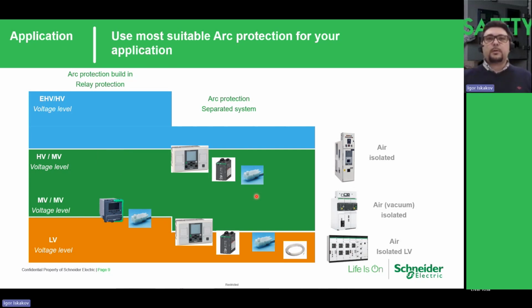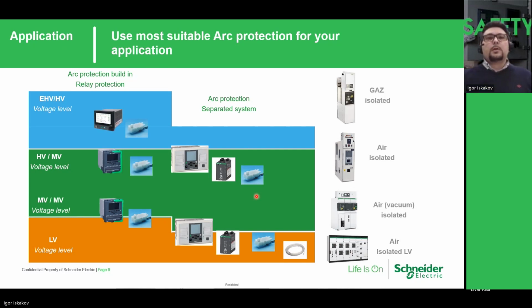If we speak about extremely high voltage, here we have gas-insulated switchgear, and actually the only place where arc flash protection sensors can be implemented is the cable ending. In these cases, we suggest a protection relay like P5, P7 or P3.